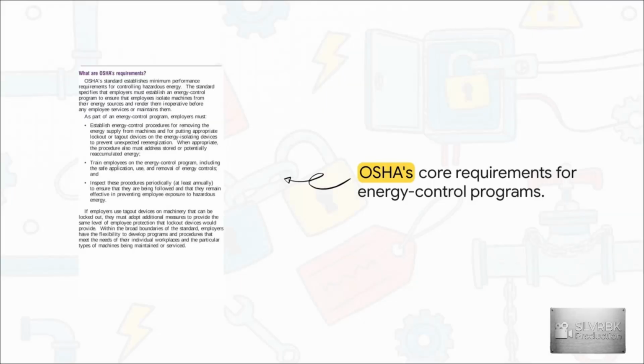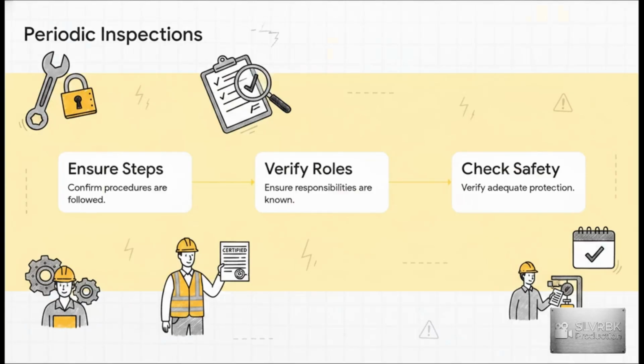As an employer, your procedures have to explicitly outline the exact steps to shut down, isolate, block, and secure your machines. Literally, no guesswork allowed. On the training side of things, you've got to ensure workers truly understand how to safely apply, use, and remove these energy controls. The authorized employees actually doing the work need to recognize the hazardous energy sources, while affected employees basically just need to understand the purpose of the procedure and, most importantly, know to never, ever tamper with a lockout device.